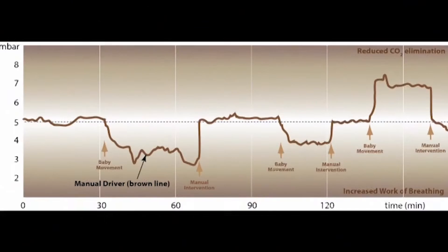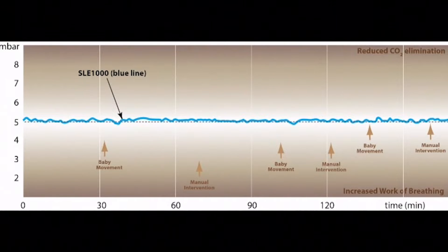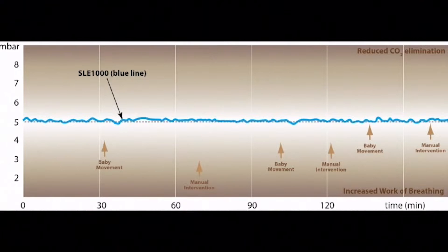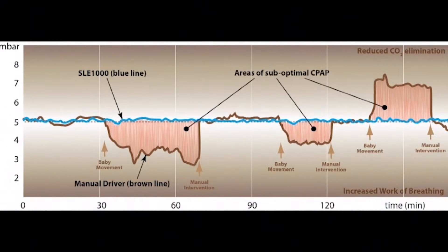The user must manually adjust the flow for changes in CPAP pressure. This graph is a simulation of CPAP using a conventional flow driver. It shows irregular CPAP delivery, which could be due to misplacement or blocked prongs or changes in lung mechanics. This second graph is a simulation of CPAP using the SLE1000 adaptive flow driver, showing the maintenance of a constant CPAP due to automatic adaptive flow compensating for pressure fluctuations. Superimposing these two graphs shows the constant CPAP delivery of the SLE1000 compared with conventional drivers. The shaded areas show periods of suboptimal CPAP when using a conventional driver.